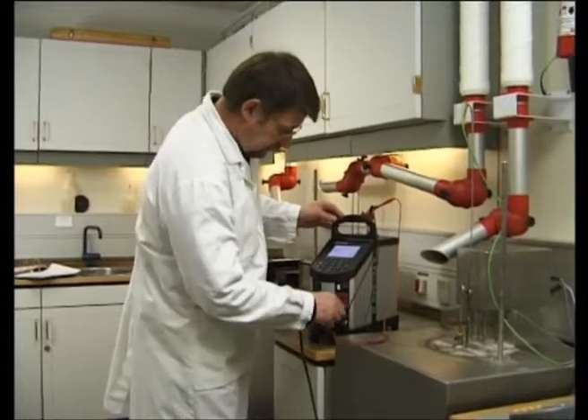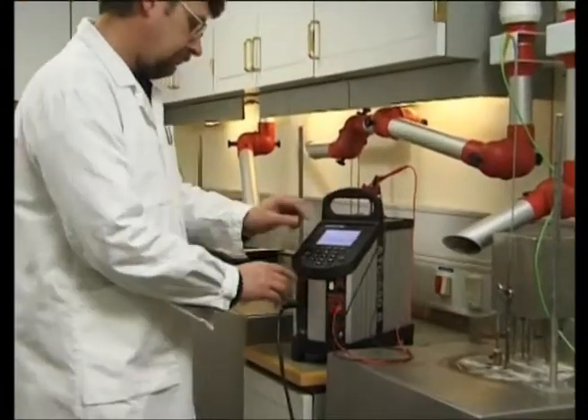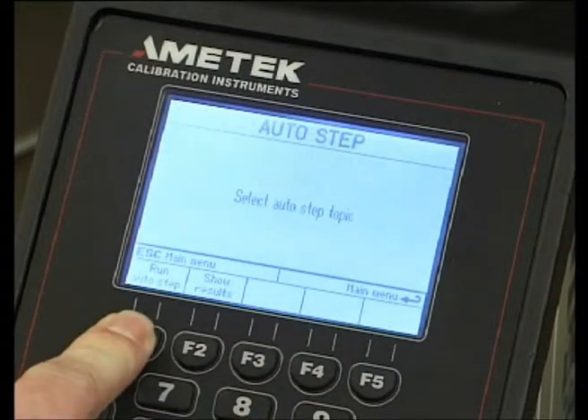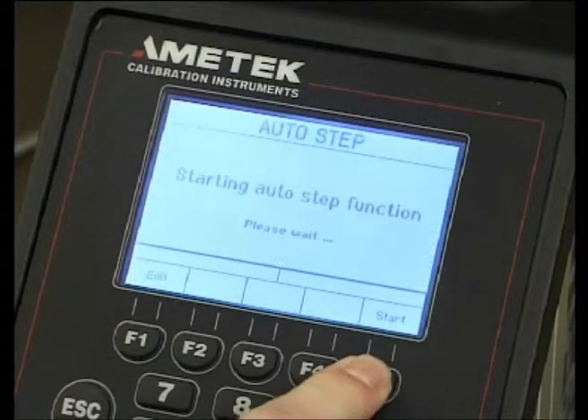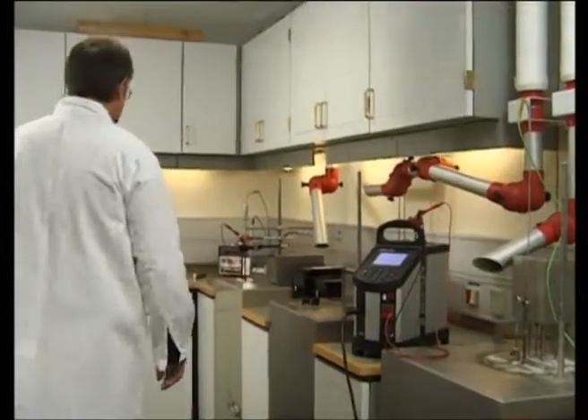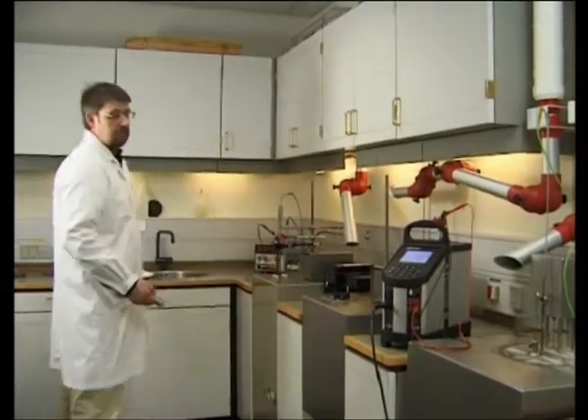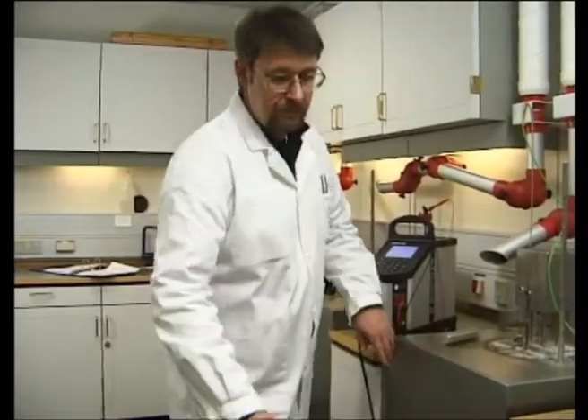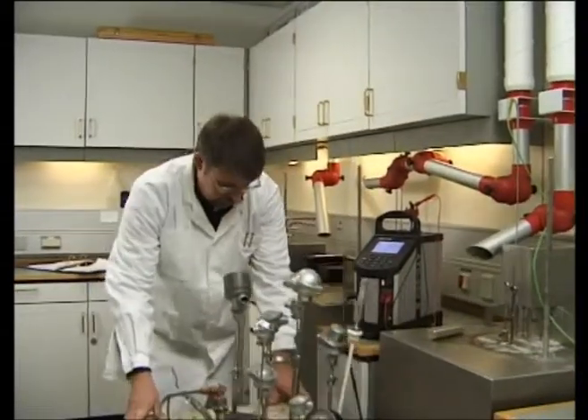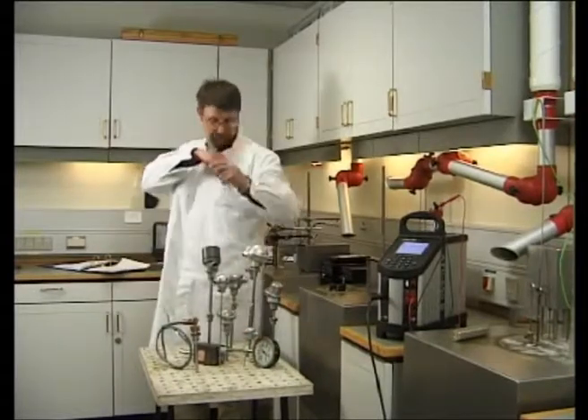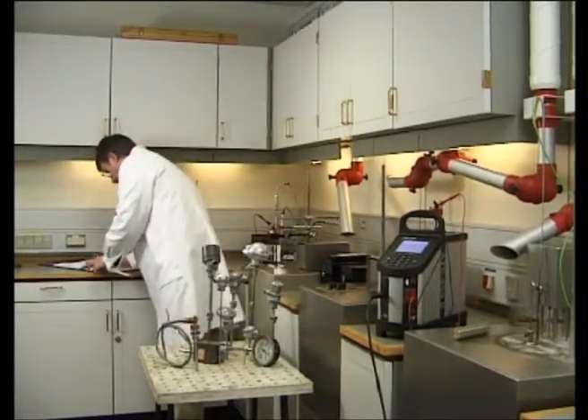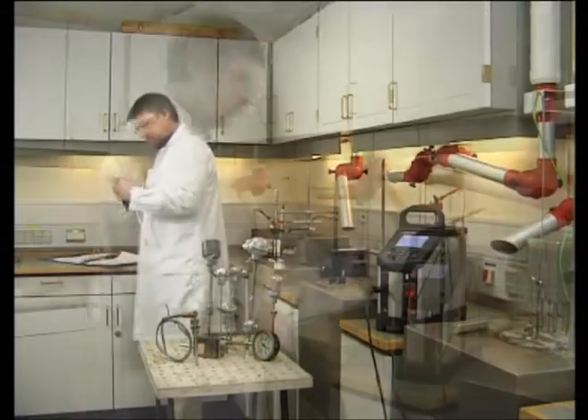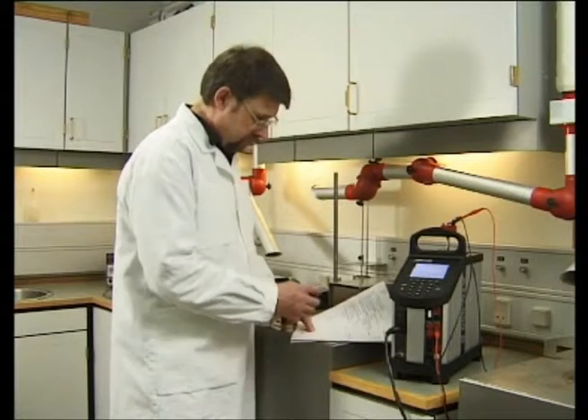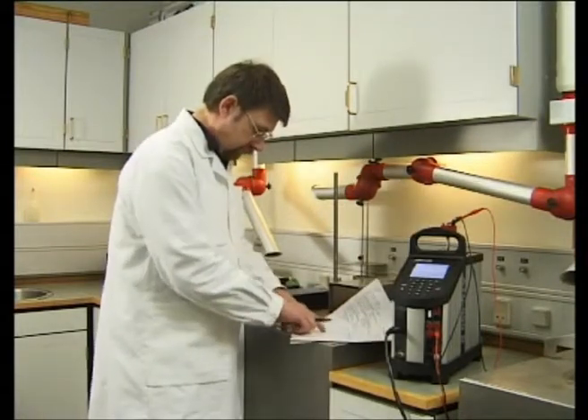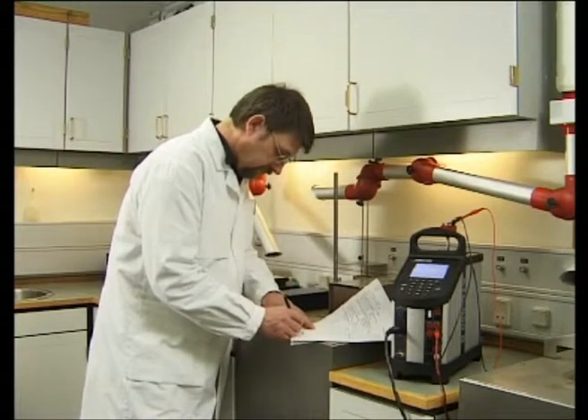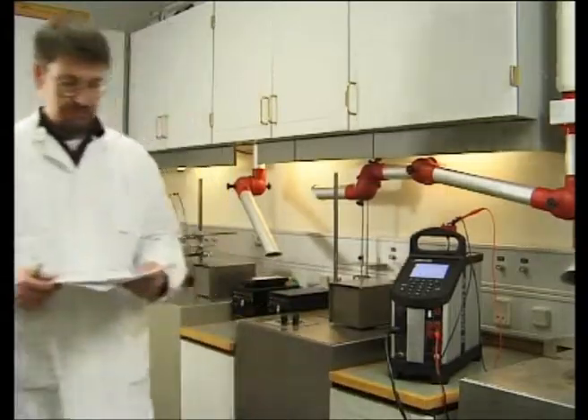Regardless of whether you calibrate in the workshop or in the calibration laboratory, the JOFRA ATC series saves you time by automating your calibration routines. The ATC series has a built-in amplifier that can measure all temperature sensor types, resistance thermometers, transmitters, milliamps, thermocouples, voltage, and thermostats. With a calibrator program for automated calibrations, you can leave the ATC calibrator and turn your attention to more pressing tasks. All data is stored, allowing you to print the certificates at an appropriate time. You save both time and money on manpower and technical resources by using our complete integrated solution.